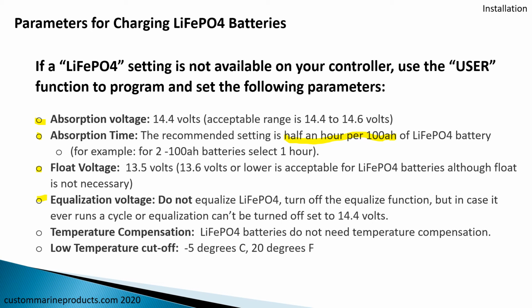Equalization, on the other hand, we do not want to equalize. Equalization is typically up around 15 plus volts. These batteries do not need equalization. The purpose of equalization is to knock the sulfates down that form on the lead plates. Well, these batteries don't have anything like that. So turn equalization off. If it can't be turned off, set it at 14.4.